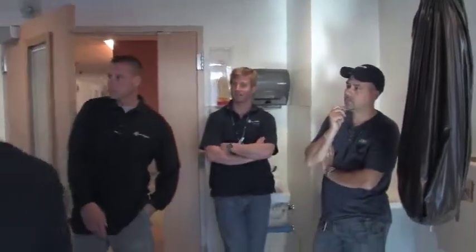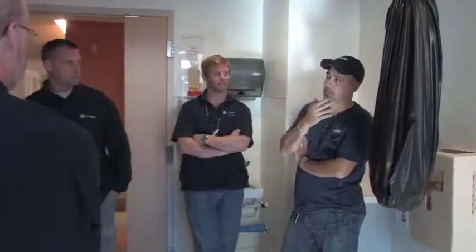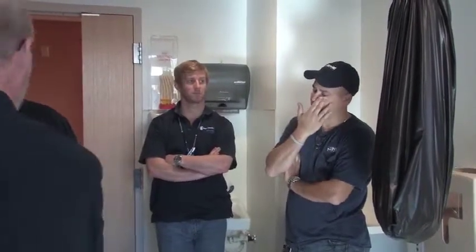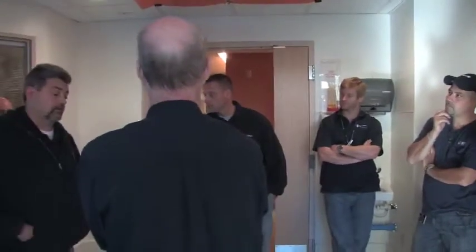That's a good thing, that you have it routed into 3 different things, so you won't get a daisy chain failure. It also helps out in communications because on these floors you have a lot of sharing of flows and temperatures, so it picks the network speed up. If you have too much, it starts bogging it down and you get slow update rates. So if you have a failure in A, B and C should be okay. That's not a bad thing.